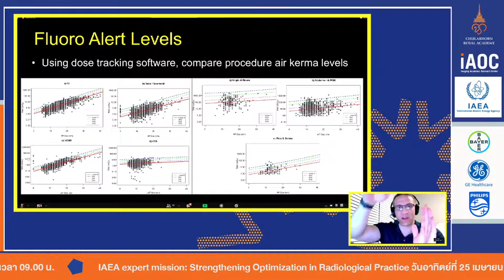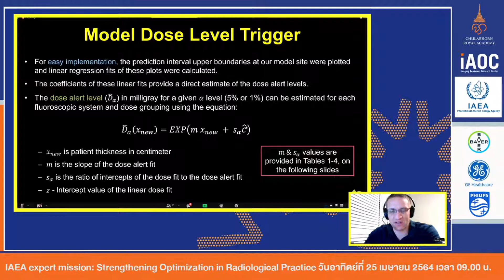And so you need to scale your doses, and that's what this equation is. This equation will allow you to scale your doses and our doses so that you can set an alert level that makes sense for your patient dose values. You'll need to know an average patient thickness. You don't need to know exactly, just a good ballpark estimate. The M value and this S sub alpha are values in some tables coming in the next slides that you'll just look up. And this C value, the C hat, forgive me, that's a typo. I shouldn't say Z, it should say C hat. That's an intercept value. This is the value that you're going to use to scale your doses so they match ours. So you can use the equation.